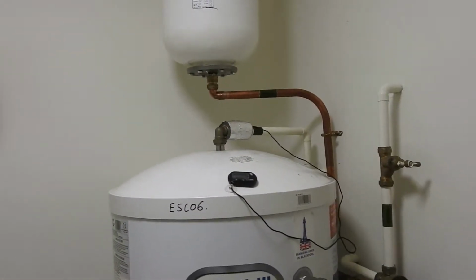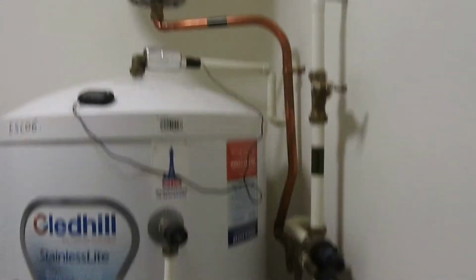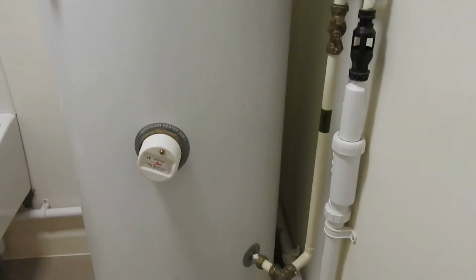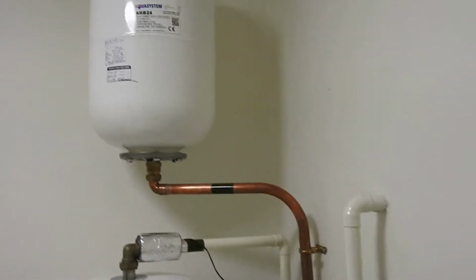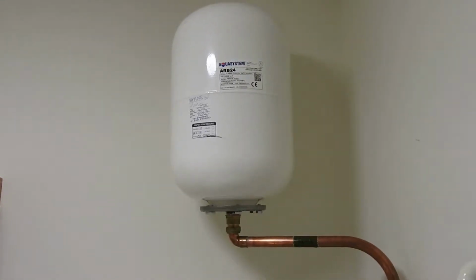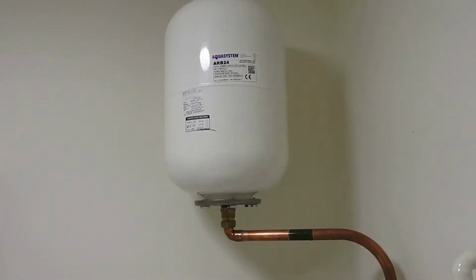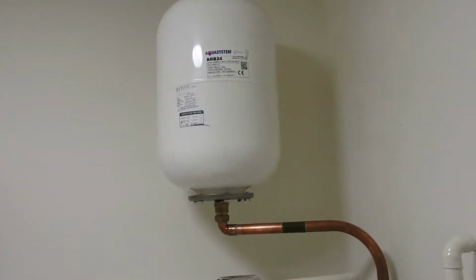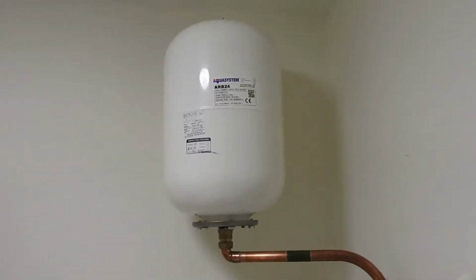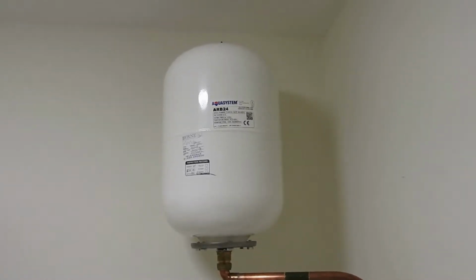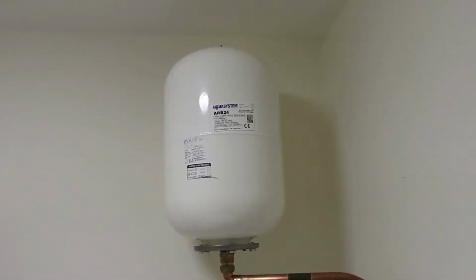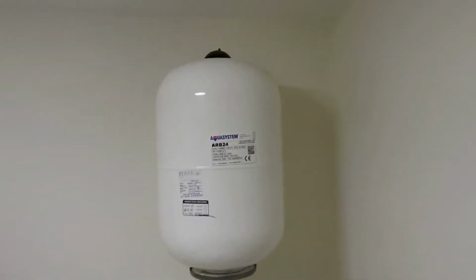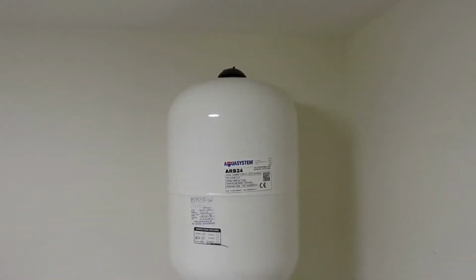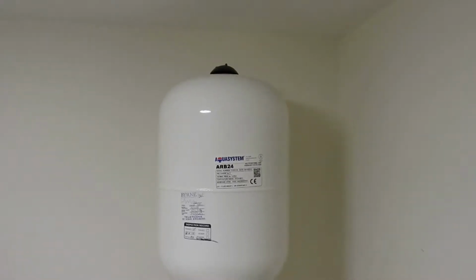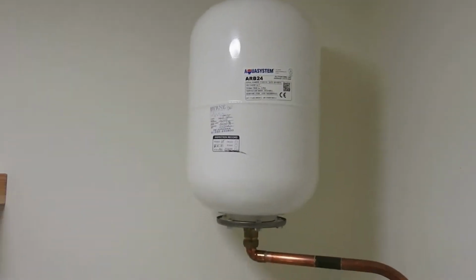Simply, as the water expands, as you can see from the bottom, it expands up into this system and goes into this tank. In there is a bladder, and that bladder has got air pumped into it like a big football, which should be at 3 bar, and we can talk about that because that's also something you might be looking after. At the top is a typical tyre valve, and you can just put a pressure gauge to the top of it and check it's at 3 bar or just below 3 bar.